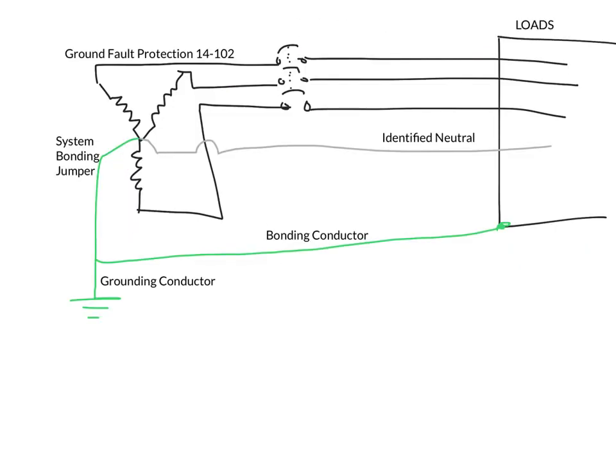Now we're going to look at ground fault protection. You can find the rules around this in section 14-102. Now, this particular type of protection is for grounded systems where high energy faults can happen, but those faults aren't necessarily going to open up the overcurrent protection, the main fuses or breakers that are protecting the circuit.